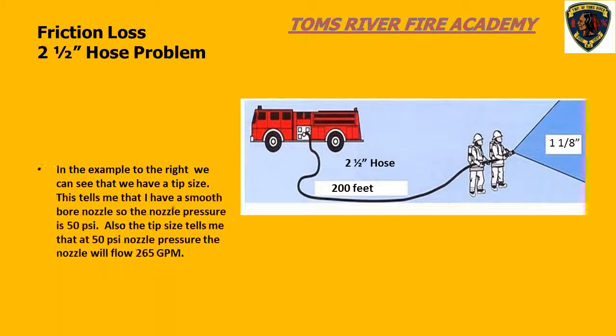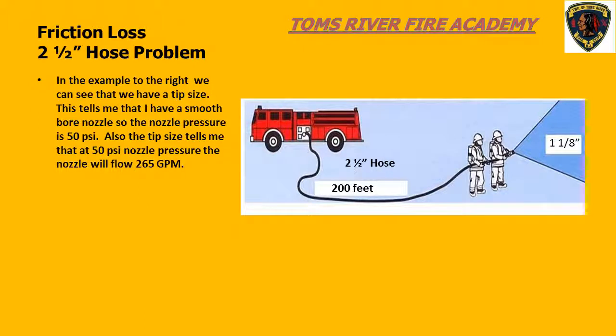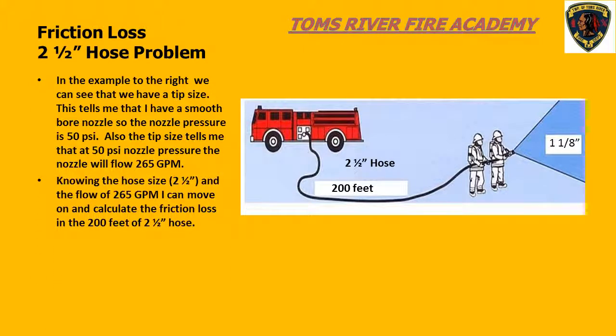In this example, we can see that we are using a nozzle with a tip size, so we know that we have a smoothbore nozzle. From lesson 2, we know that a smoothbore nozzle on a hand line requires 50 PSI nozzle pressure. We are given a tip size of 1⅛ inch. From our nozzle flow chart, we know that a 1⅛-inch tip will flow 265 gallons per minute. We also know the length, which is 200 feet. We now have all the needed information to use the rule of thumb formula for calculating friction loss in 2.5-inch hose.